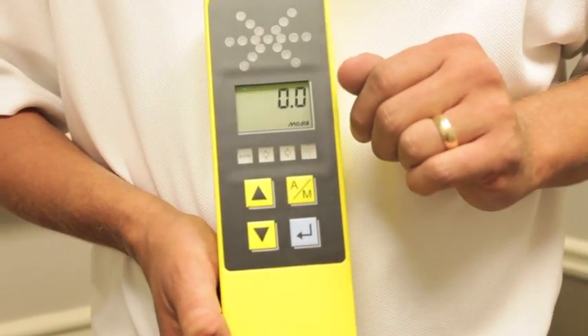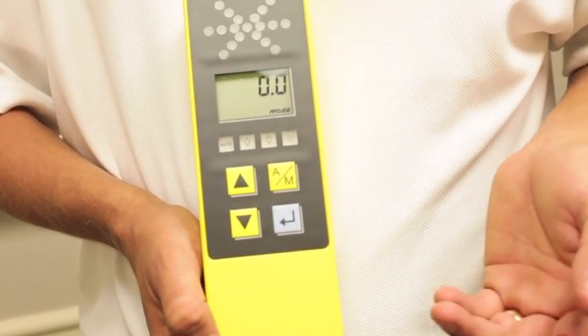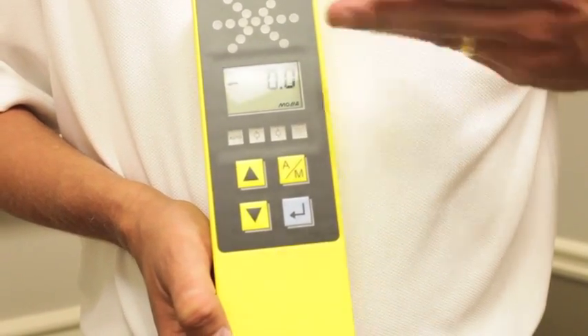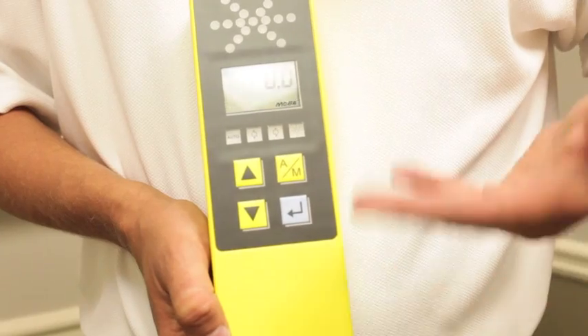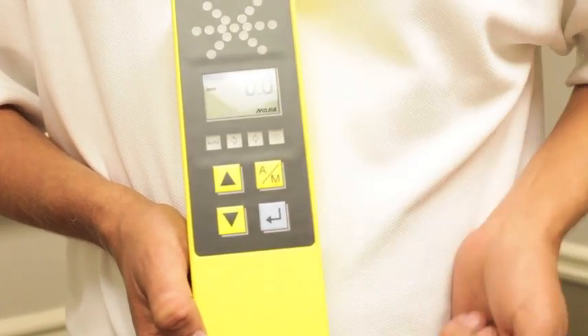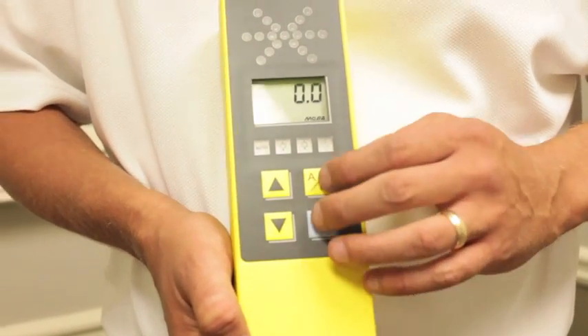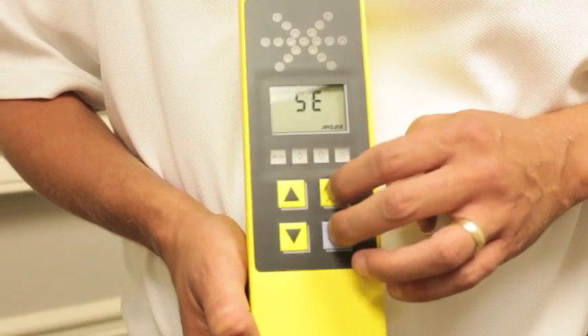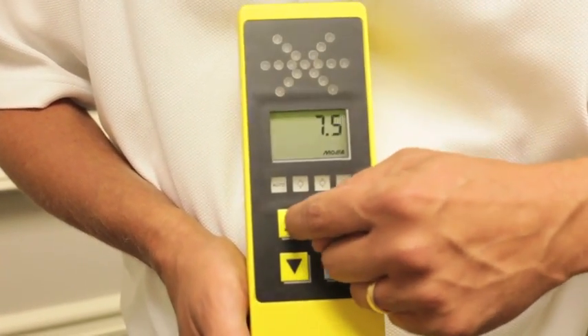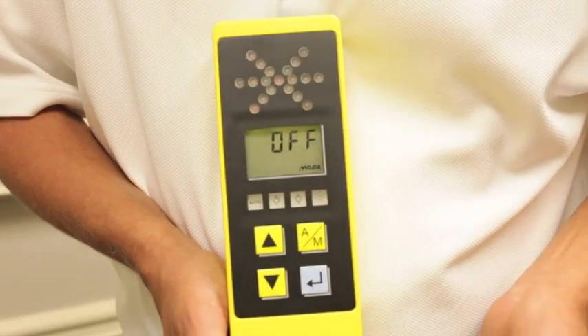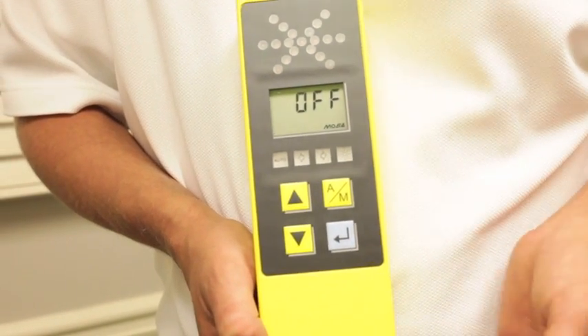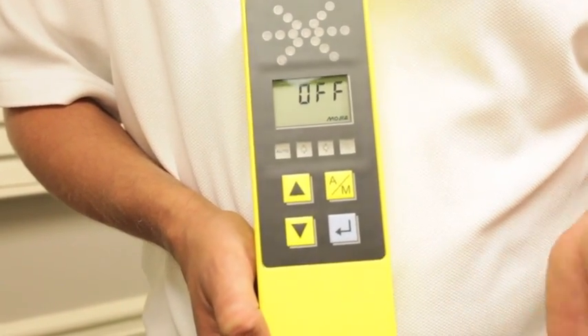Some people set that too low, set it at an inch, inch and a half, so if they have something like the road's bouncing up and down, they'll put in kind of a constant alarm mode and people think something is wrong. It's just their working window is set to the wrong number. To change that working window, arrow it up. A lot of people will just turn it off. You arrow it up past 7.9, it will go off, and some people leave it there. And that's how you go through the main operators menu and what each icon means.